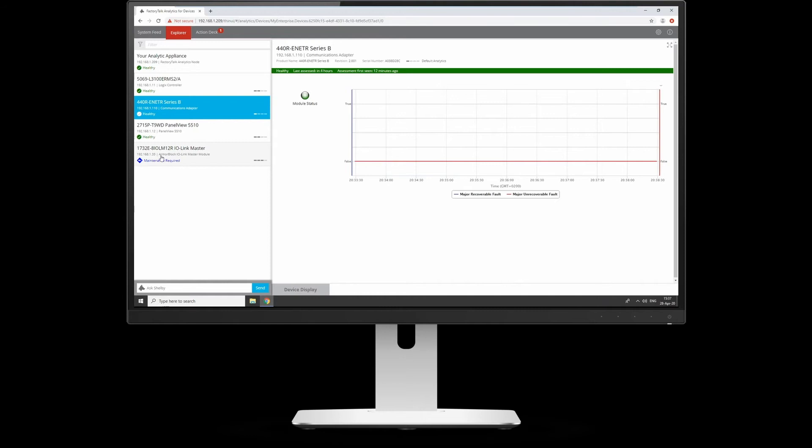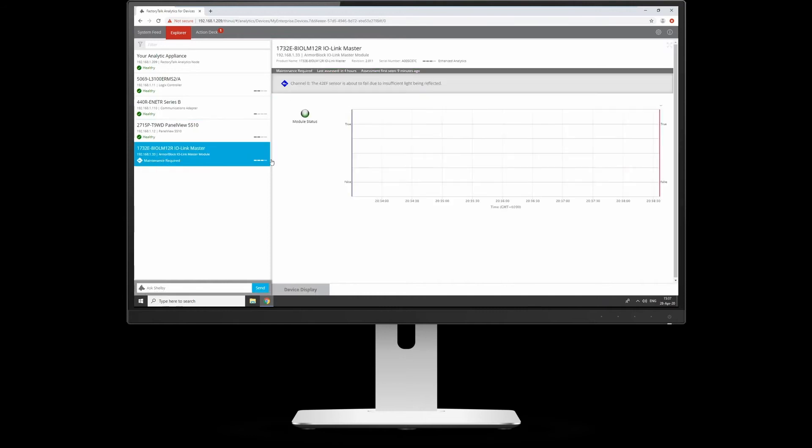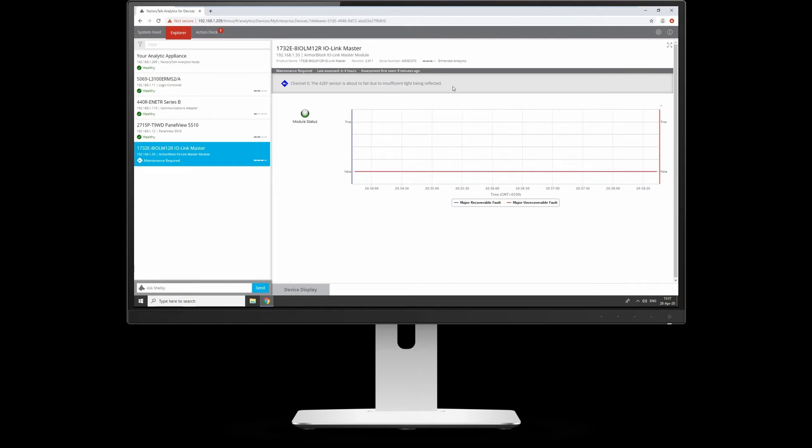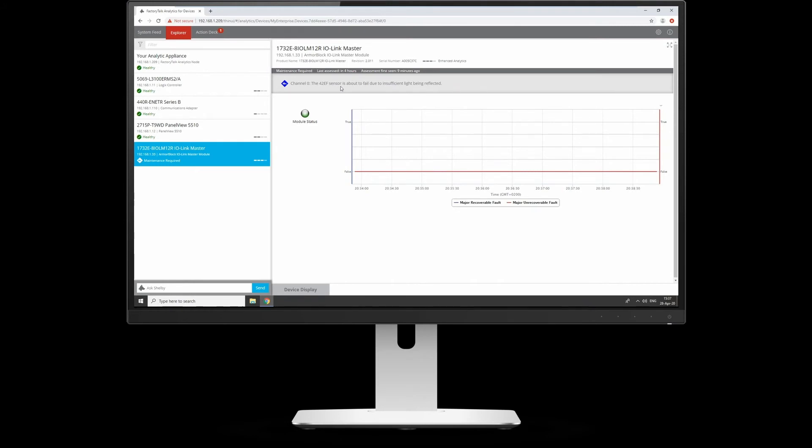If we go in there, it's giving you in plain English that on channel zero, it even tells me the sensor type. A 42EF sensor is about to fail because it's getting insufficient light detected. In the earlier demo, we had the IO-Link Master and said it needed cleaning. Basically it's telling me the sensor's still working, but your maintenance guy should really go have a look at it.